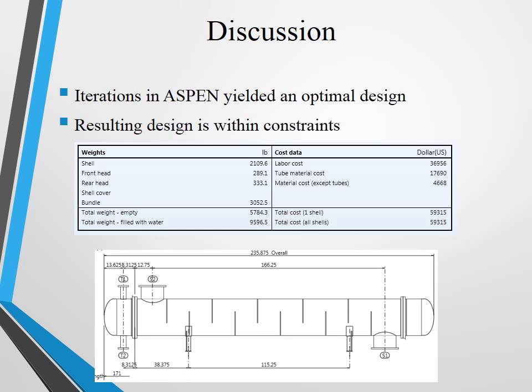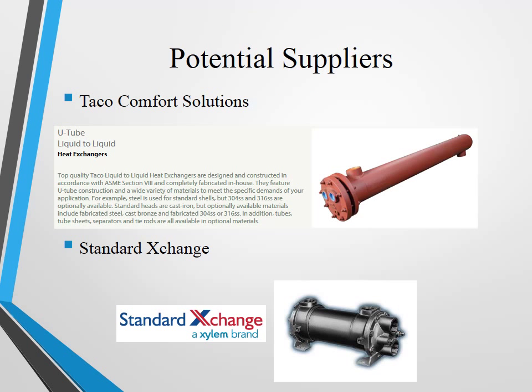The figures below summarize the cost, weight, and spatial geometry of the design. The price of one heat exchanger was calculated to be about $59,000. Additionally, since the heat exchanger might be subject to fouling, cleaning the system was considered. The shell could be cleaned with a safe solvent flush, whereas the tube side containing the propylene glycol could be cleaned mechanically with a water jet. From a search for potential suppliers, we found these heat exchanger manufacturers suitable for our application.